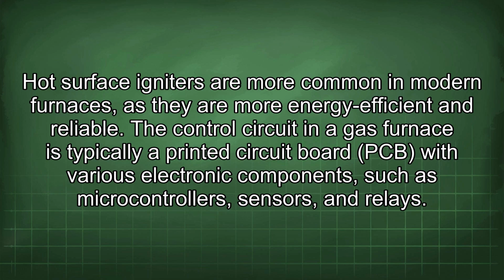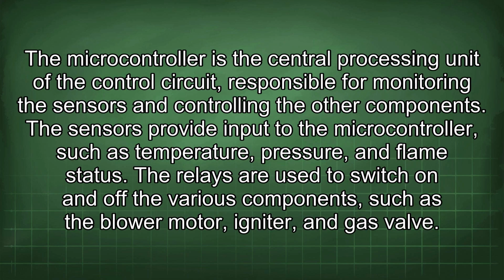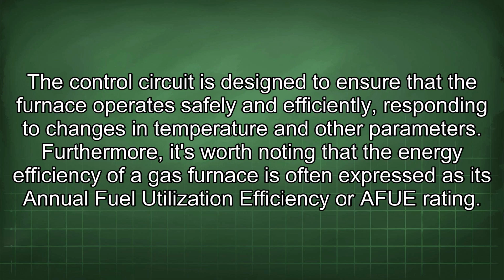The control circuit in a gas furnace is typically a printed circuit board (PCB) with various electronic components such as microcontrollers, sensors, and relays. The microcontroller is the central processing unit of the control circuit, responsible for monitoring the sensors and controlling the other components. The sensors provide input to the microcontroller, such as temperature, pressure, and flame status. The relays are used to switch on and off the various components such as the blower motor, igniter, and gas valve.